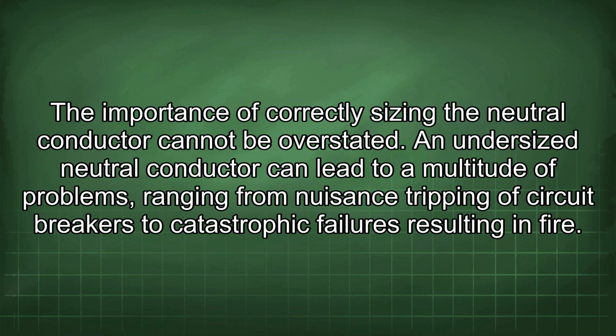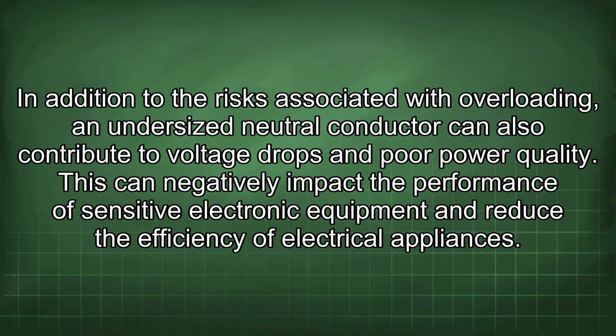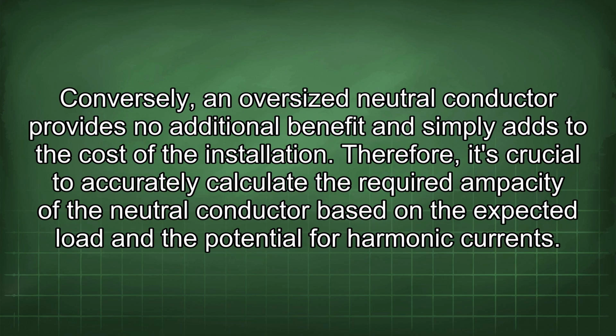The importance of correctly sizing the neutral conductor cannot be overstated. An undersized neutral conductor can lead to a multitude of problems, ranging from nuisance tripping of circuit breakers to catastrophic failures resulting in fire. In addition to the risks associated with overloading, an undersized neutral conductor can also contribute to voltage drops and poor power quality. This can negatively impact the performance of sensitive electronic equipment and reduce the efficiency of electrical appliances. Conversely, an oversized neutral conductor provides no additional benefit and simply adds to the cost of the installation.